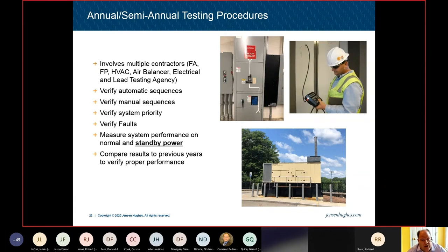But one of the final tests we do is we create a sprinkler water flow from an inspector's test connection up in the building. That's going to start a water flow for the floor and turn the fire alarm system on. If it's a high-rise building, after the pre-alert, three floors will go into alarm. The fire pump kicks on, and we do this all under normal power. So the speakers are going off, the strobes are going off, the fire pump's running, the stair pressurization fans are running. There's a lot of stuff in the building running, and we're all on normal power. And then we kill building power.